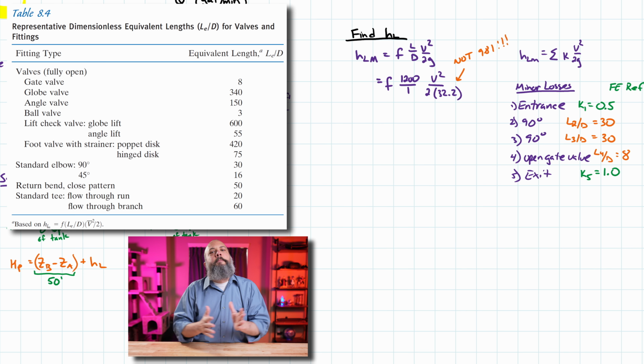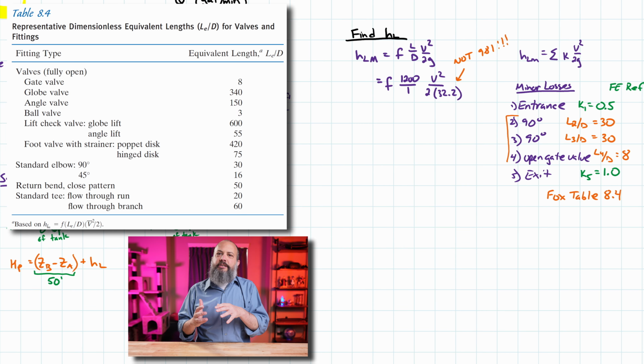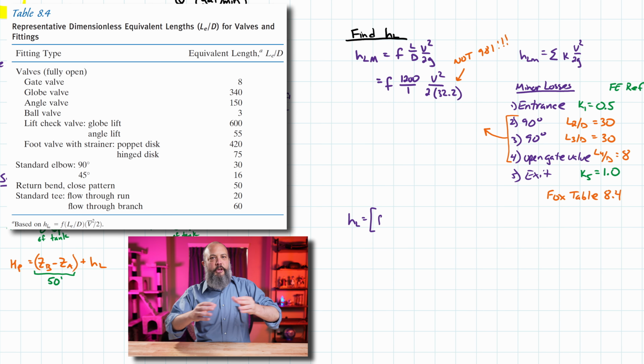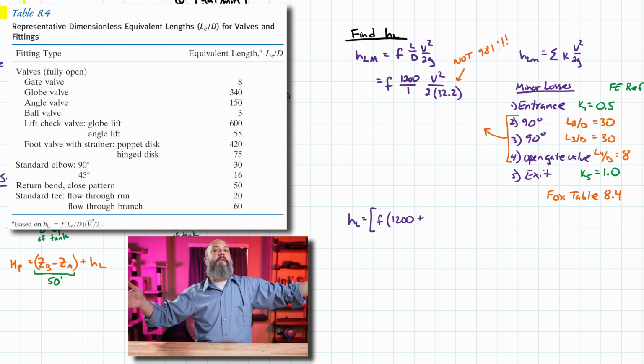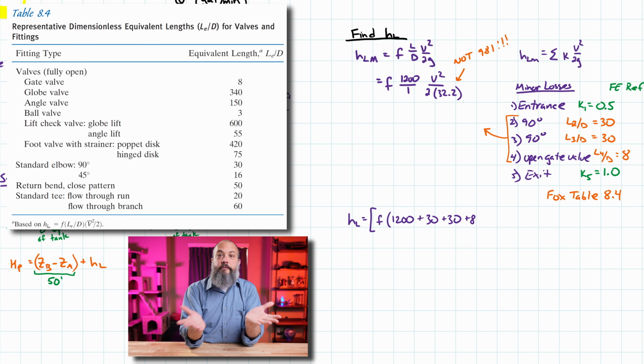It seems really high. What this L over D, this 30, actually represents is an equivalent length. So this table doesn't treat minor losses like a K term. Instead, we're treating these like length over D on the friction side of the equation. We're essentially saying that this 90-degree bend makes it seem as if the overall pipe, instead of being 1,200 feet long, is an extra 30 feet longer. It's 1,230 feet long, so it gets multiplied by friction.